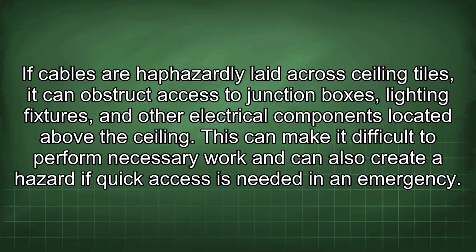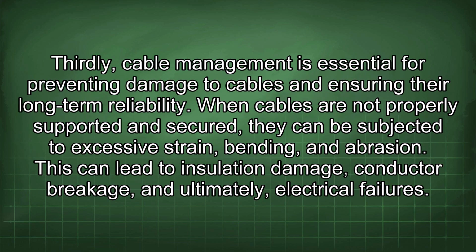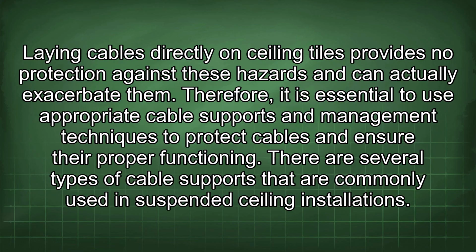This can make it difficult to perform necessary work and can also create a hazard if quick access is needed in an emergency. Thirdly, cable management is essential for preventing damage to cables and ensuring their long-term reliability. When cables are not properly supported and secured, they can be subjected to excessive strain, bending, and abrasion. This can lead to insulation damage, conductor breakage, and ultimately, electrical failures. Laying cables directly on ceiling tiles provides no protection against these hazards and can actually exacerbate them. Therefore, it is essential to use appropriate cable supports and management techniques to protect cables and ensure their proper functioning.